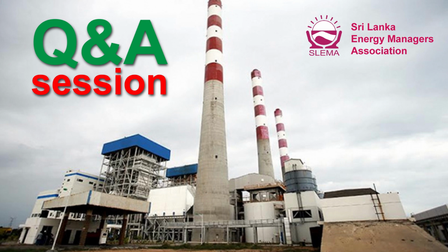Now, keeping a boiler and equipment on standby is somewhat costly, right? Keeping it ready means that firing the boiler takes time. After firing, it takes about 5 to 8 hours to synchronize it to the grid. So if the other standby unit needs to be ready during an emergency situation, that means it has to be fired. So that's not a good condition. And of course, the situation of employing a diesel generator is being looked at.